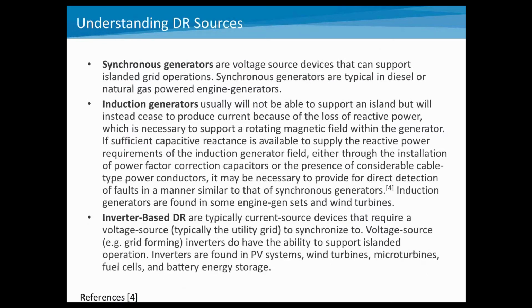Just to cover some highlights with understanding your DER, or distributed resources, there's basically three different kinds. You may have a synchronous generator, and typically these are voltage source devices, something like a diesel generator or a natural gas powered engine genset, realizing that those can definitely support island grid operations. Induction generators typically are not able to support an island, because of the need to supply reactive power for an induction generator. Of course, if there's sufficient capacitance, like capacitor banks inside that potential island, that needs to be evaluated.